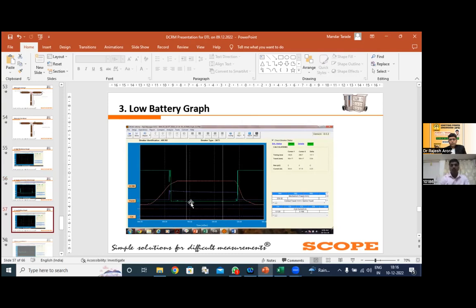Now, one more important thing is that in many cases, people get the zero touch on the DCRM resistance curve. The probable reason for the zero touch is that your current is not healthy. You are not injecting the full current, or your source is not delivering the proper current. That's why you are getting the zero touch, or your test lead set is not healthy.